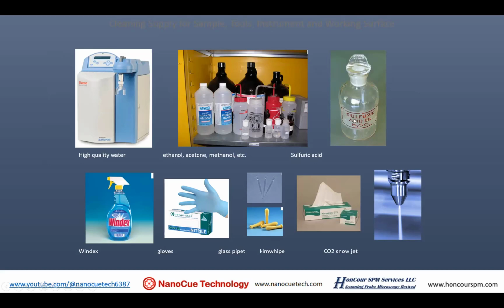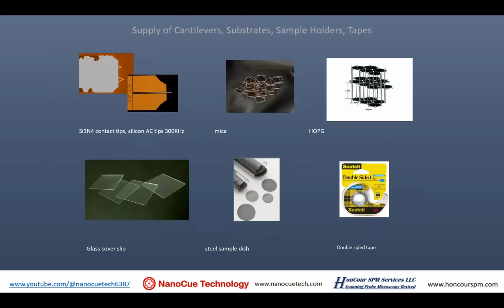Sulfuric acid, that's needed if you really want to clean your liquid cell, because you need to burn away all the organic contaminations using sulfuric acid. That's for extremely high cleanliness requirements, for example, electrochemistry. Substrate, you need to maintain a good supply of substrate, for example, graphite, HOPG, mica, glass slides, and then these steel sample dishes are very important. And double-sided tape is a must, because that's how you fix some of the samples on the steel dish.